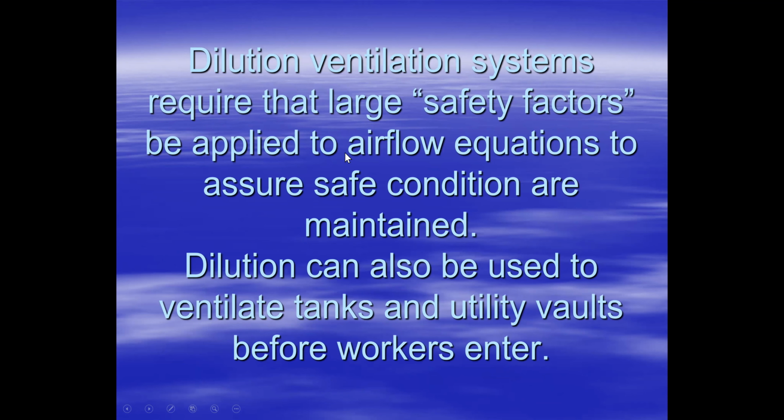So we're putting those fairly large safety factors in to take into account that some of our assumptions that are built into the calculations may not be 100% accurate, and therefore I need to bring in more air than I had planned on.